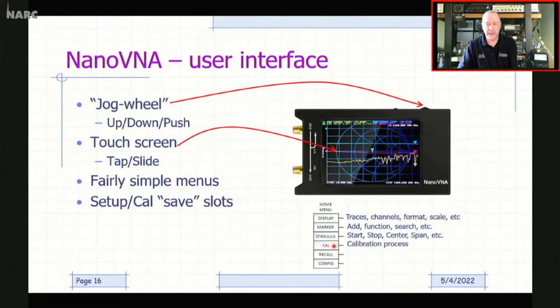When you do a user calibration, there are save slots, meaning little memory that's allocated to that. When you finish a calibration, you can save the result of that calibration in this little memory slot, so that if you go to repeat a measurement under the same conditions later on, you don't have to repeat the calibration. You can just load up that saved calibration state.